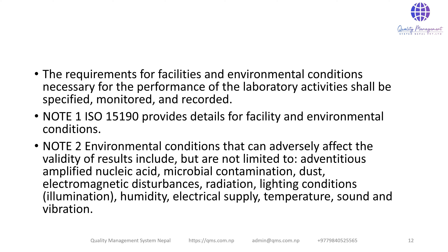ISO 15190 provides details for facility and environmental conditions. Environmental conditions that can adversely affect the validity of results include, but are not limited to: amplified nucleic acid, microbial contamination, dust, electromagnetic disturbances, radiation, lighting conditions, illumination, humidity, electrical supply, temperature, sound, and vibration.